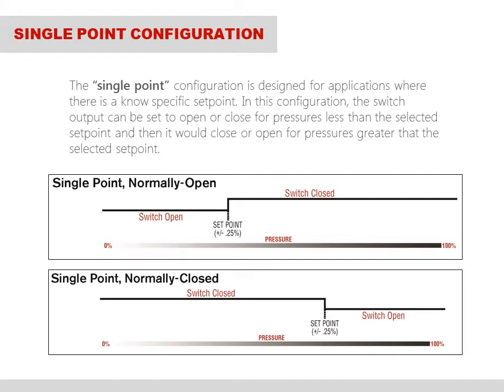So the switch is normally open and closes when the process pressure rises, and opens again when the process returns to a pressure at or below the set point. You can see that the lower diagram is just the opposite of the upper diagram.